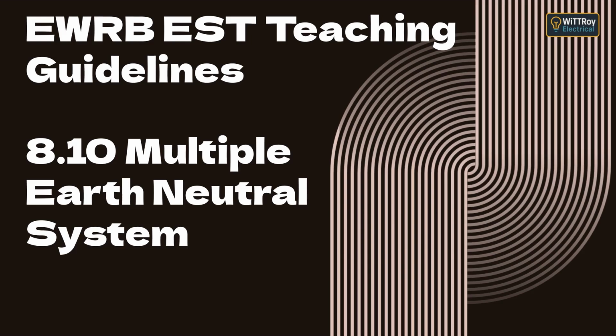Topic B, why the neutral is earthed at multiple points. The neutral is earthed at many points in the supply to make the system safer and more reliable. By having several earthing points, we keep the neutral to earth voltage very low, reduce the risk of a broken neutral becoming dangerous, and ensure the voltage between any exposed metalwork and true earth never rises too high. If the neutral were only earthed at one point, a fault anywhere along the line could make the whole neutral system rise to live potential. So, multiple earthing adds redundancy and stability.